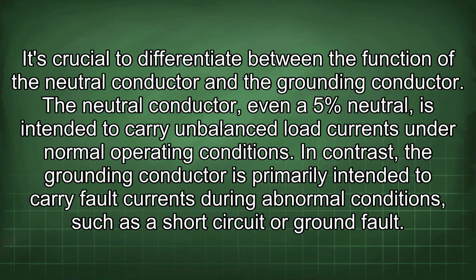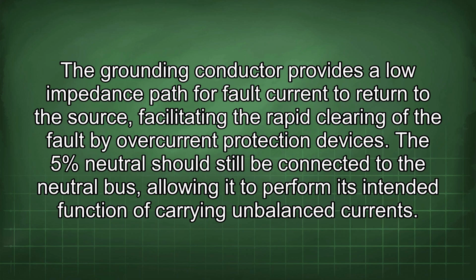It's crucial to differentiate between the function of the neutral conductor and the grounding conductor. The neutral conductor, even a 5% neutral, is intended to carry unbalanced load currents under normal operating conditions. In contrast, the grounding conductor is primarily intended to carry fault currents during abnormal conditions such as a short circuit or ground fault. The grounding conductor provides a low impedance path for fault current to return to the source, facilitating the rapid clearing of the fault by overcurrent protection devices.